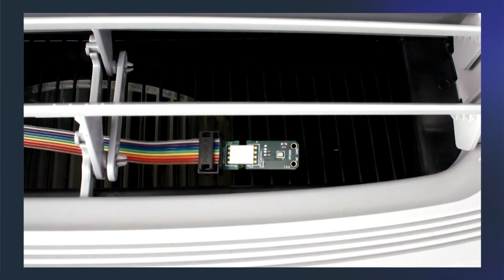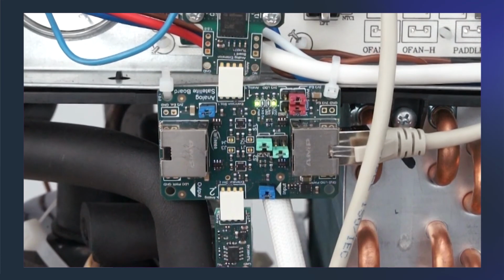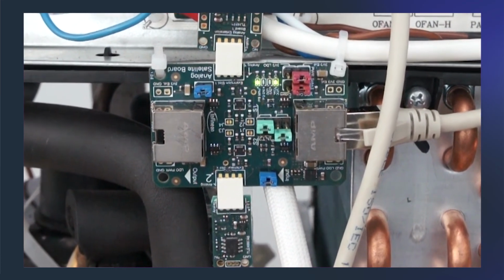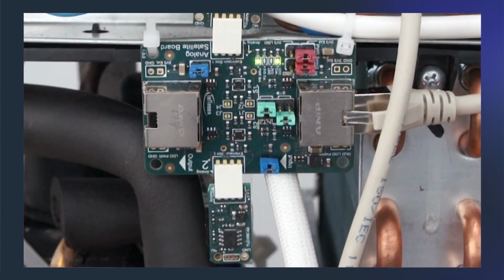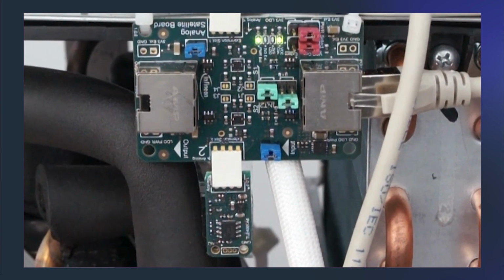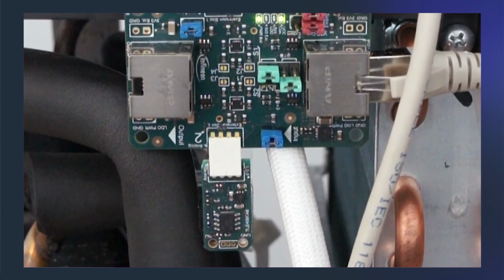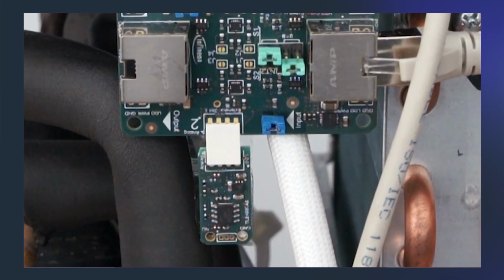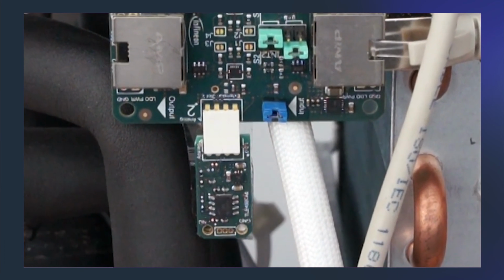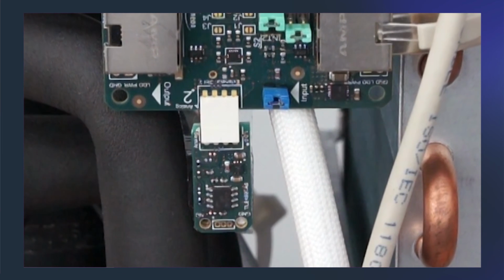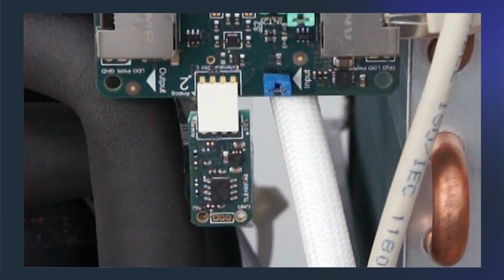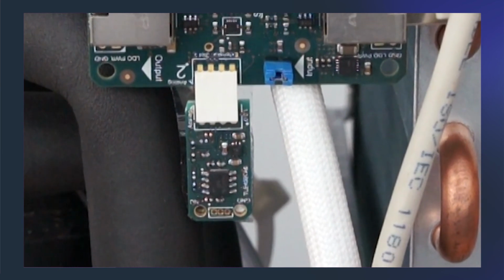We have also attached a linear Hall sensor. Here it is. It is attached near the compressor body, but has no mechanical connection with it. It is an analog sensor, which is used to sense magnetic fields, which vibrate because of the compressor vibration. The spectrum of its signal is pretty clean when the compressor works fine, as expected, and could be dirty and full of harmonics in case of problems such as an unscrewed nut or a bearing break.